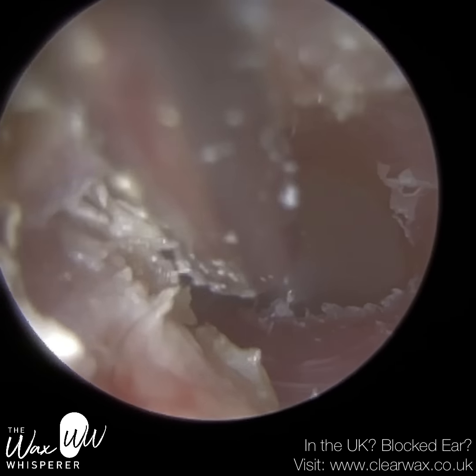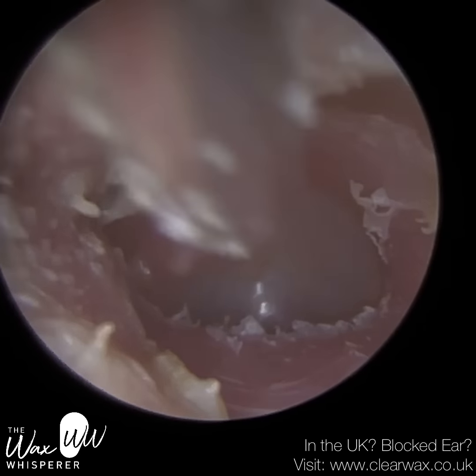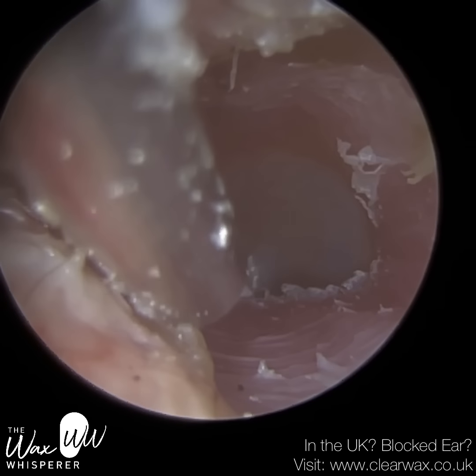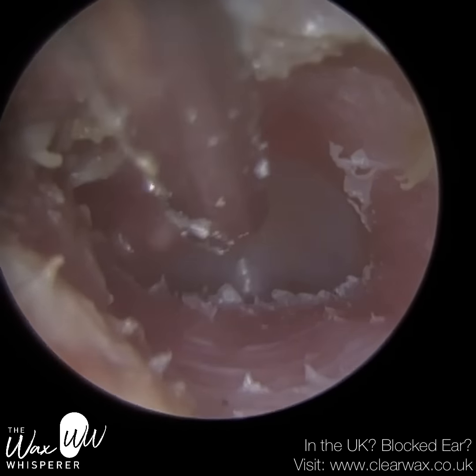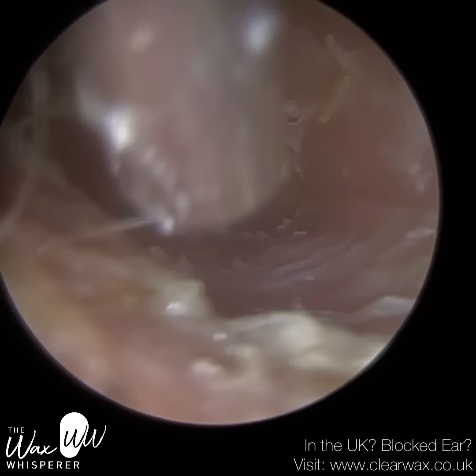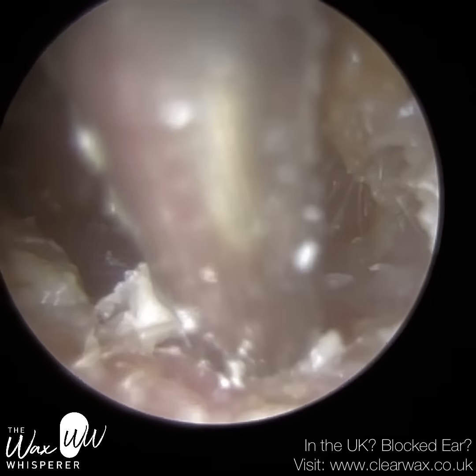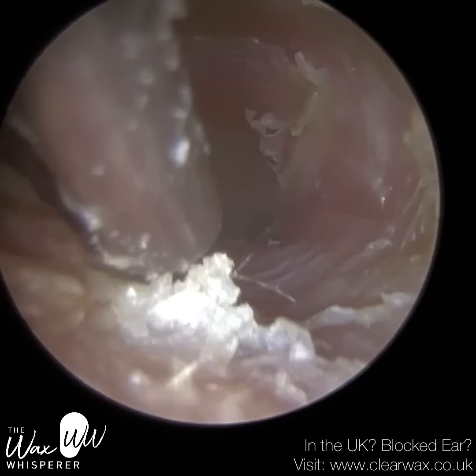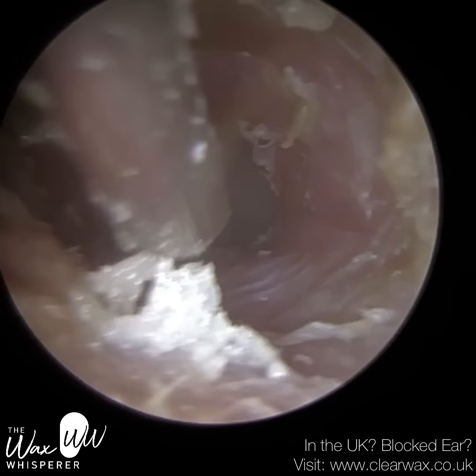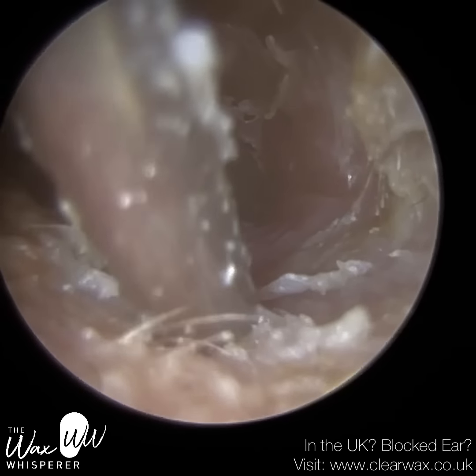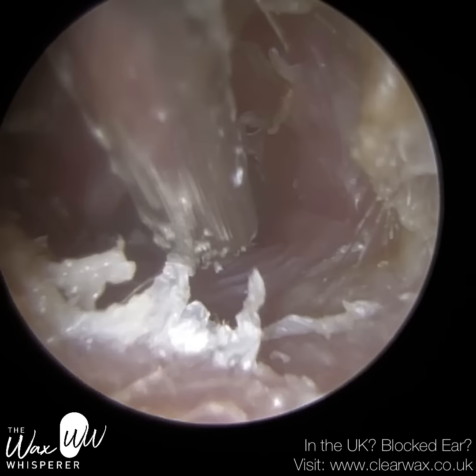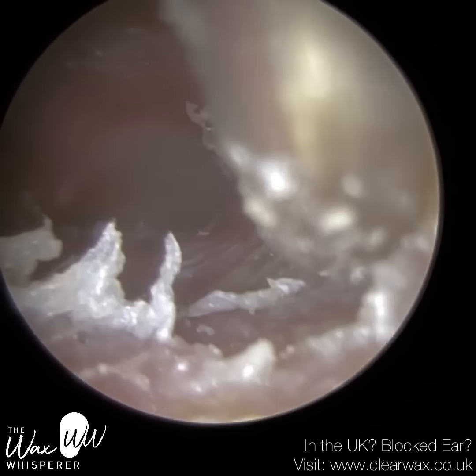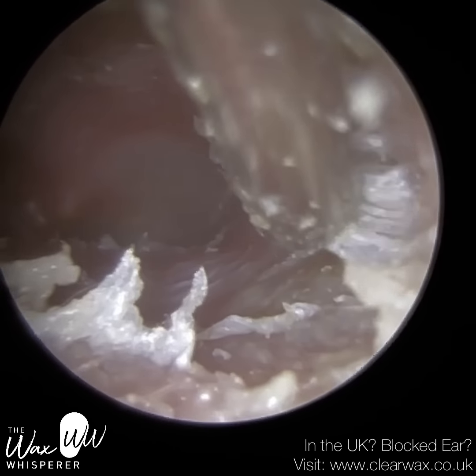Now, the endoscope itself never gets hot. We generally get this a lot in the UK. There's always, for whatever reasons, obviously political reasons and for self-gain, this myth going around that you can't use an endoscope to remove earwax because it's so hot and it'll scald the ear canal. Well, that's completely false.